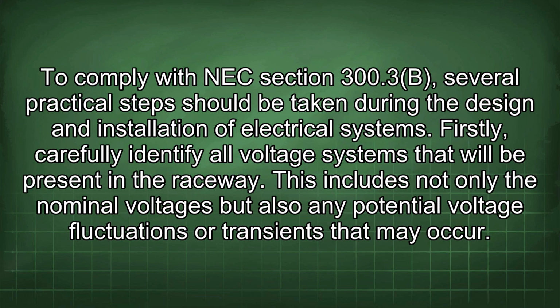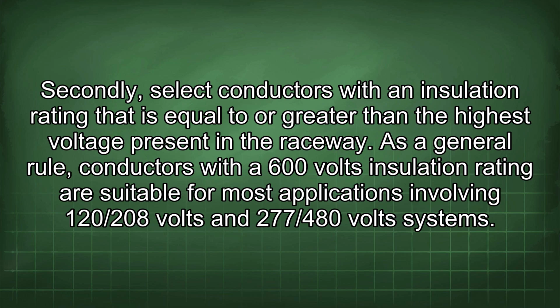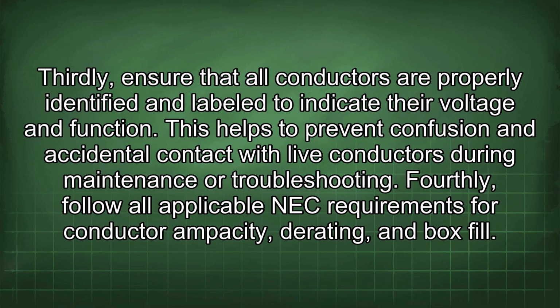To comply with NEC Section 300.3(B), several practical steps should be taken during the design and installation of electrical systems. Firstly, carefully identify all voltage systems that will be present in the raceway. This includes not only the nominal voltages but also any potential voltage fluctuations or transients that may occur. Secondly, select conductors with an insulation rating that is equal to or greater than the highest voltage present in the raceway. As a general rule, conductors with a 600 volt insulation rating are suitable for most applications involving 120/208 volt and 277/480 volt systems.